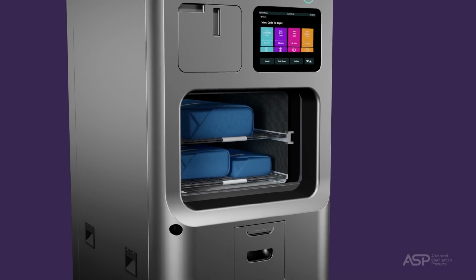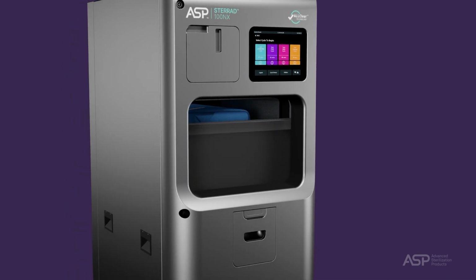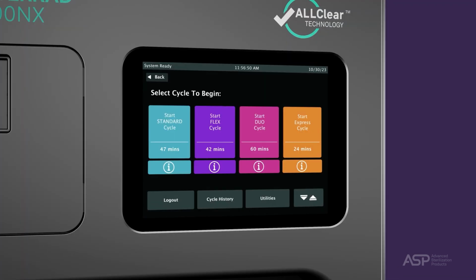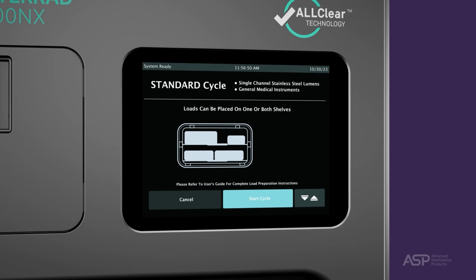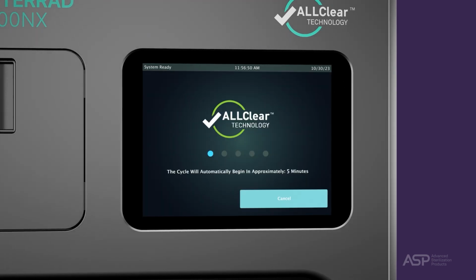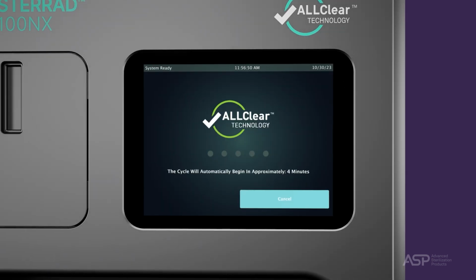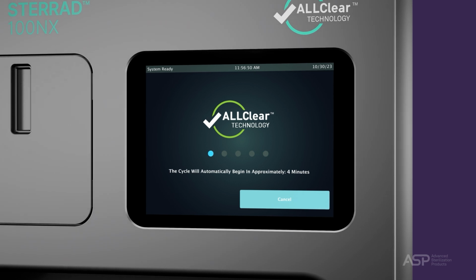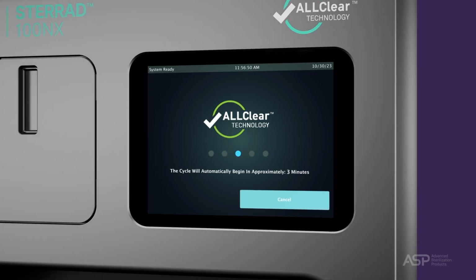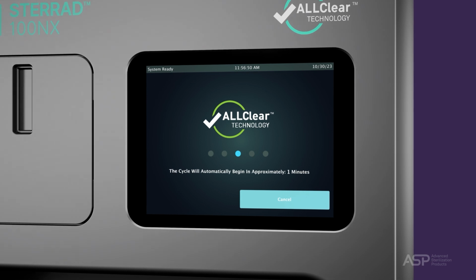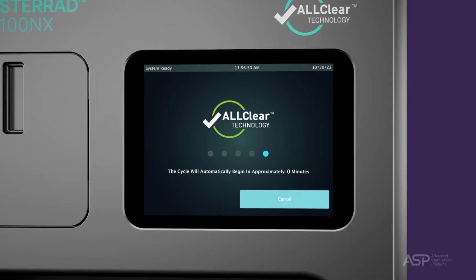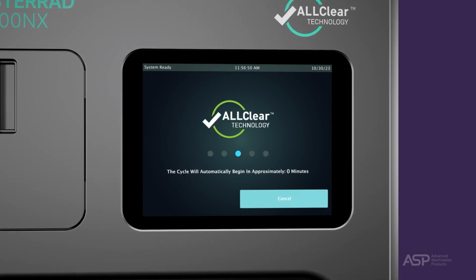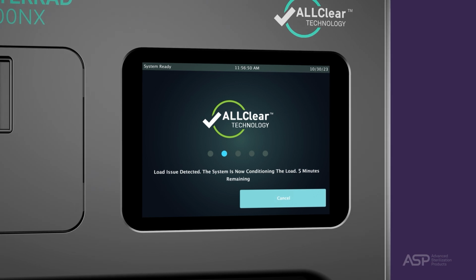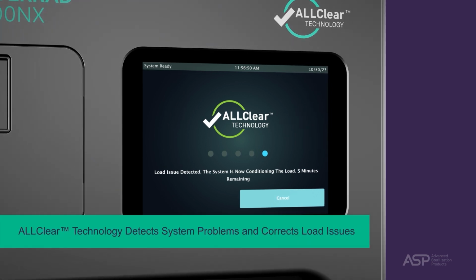Prior to beginning the cycle, the STERRAD 100NX sterilizer with ALLClear technology will run an automatic pre-cycle system diagnosis and load conditioning phase. The load conditioning process minimizes the number of sterilization cycle cancellations by detecting system problems and correcting load issues. This process completes in about 5 minutes and occurs prior to the start of the selected sterilization cycle. If a load issue is detected, the sterilizer will attempt to correct it.